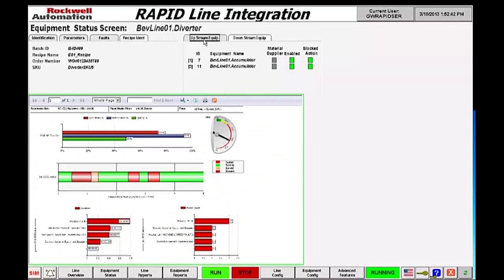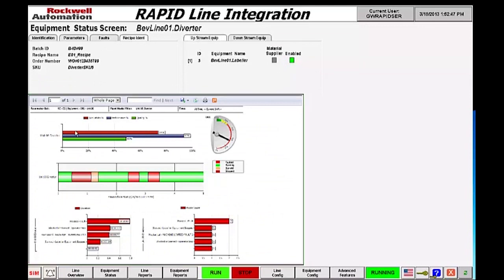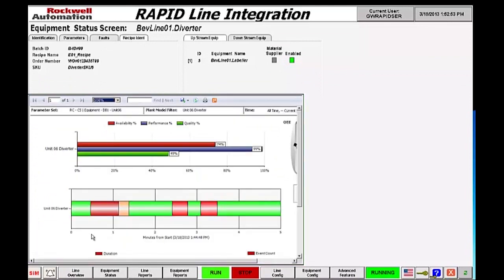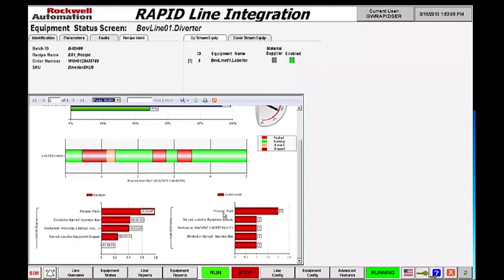Additionally, the actual equipment configuration is shown for up and downstream systems. In the bottom section is the most valuable information. Each machine has its own associated OEE dashboard report. The actual dashboard report shows the three components of OEE — availability, performance, and quality — in the top section, as well as the overall machine state across the duration of the production run. In the bottom section is the total durations and total quantity of events of downtime associated with this machine.